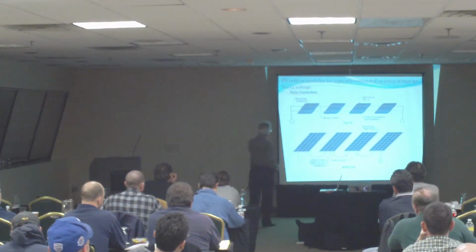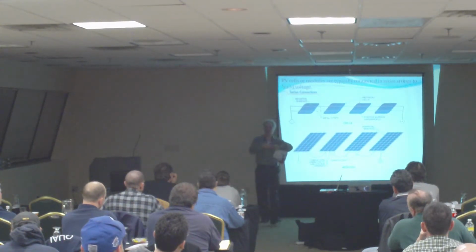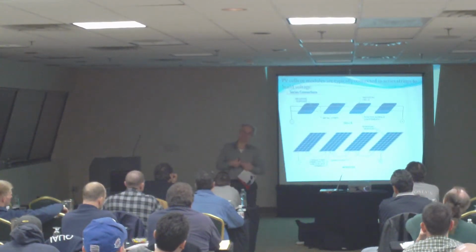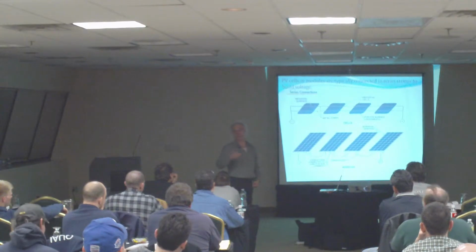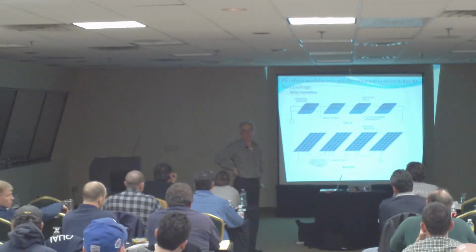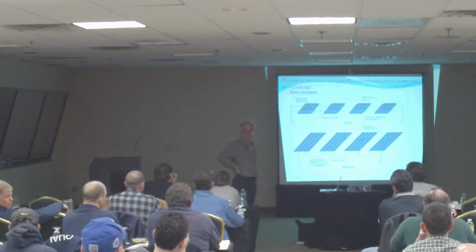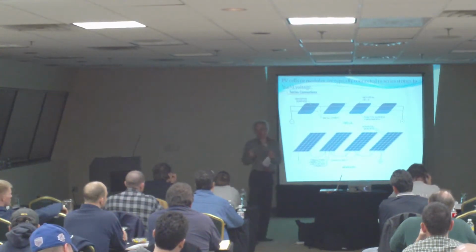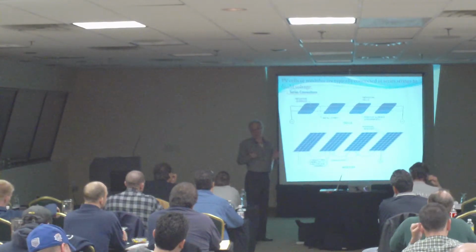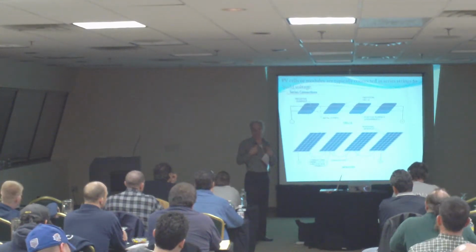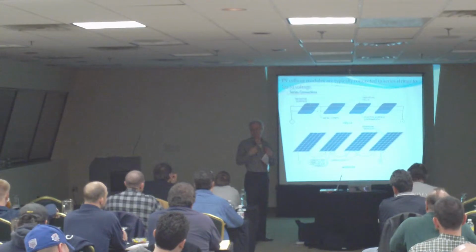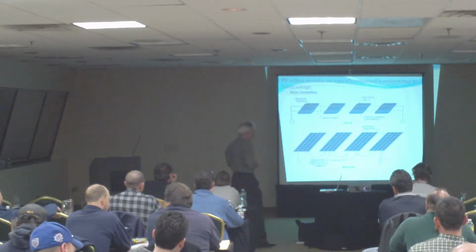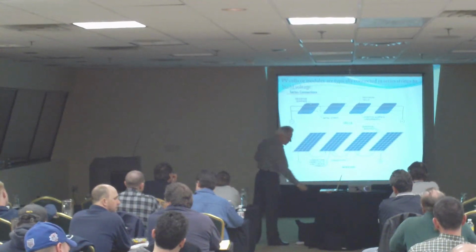If I take those leads and short them together, all of them now, and measure the current in here, the short circuit current of the system under these conditions, I will measure close to the expected value that I have. But there is some current, and that's one of the ways I'm going to test it. If I'm going up on the roof and I want to test the panel, how are you going to test it? In some cases, I'll take the panel and short the things together, see if I get any current flow. Well, we're going to actually be testing and so forth.